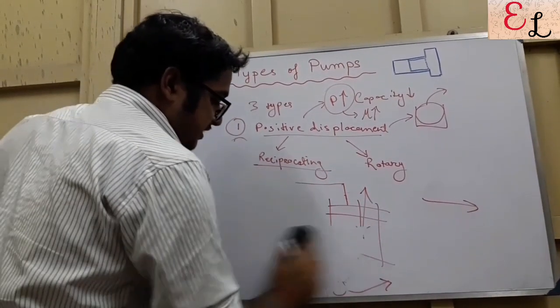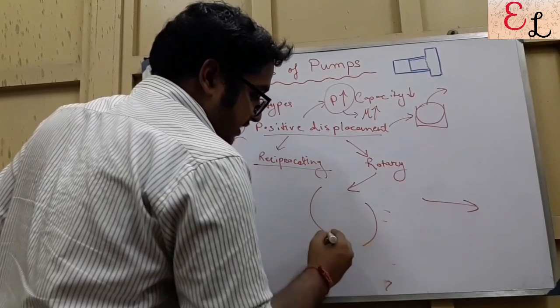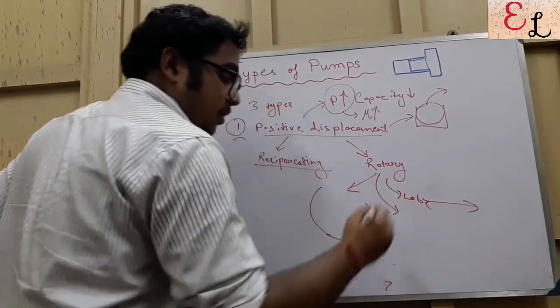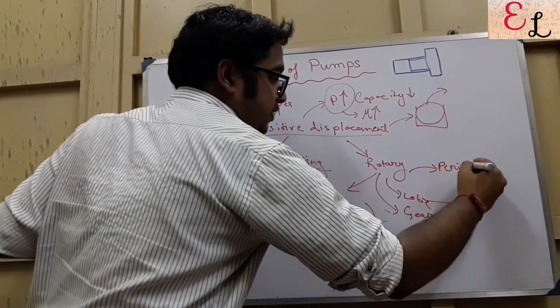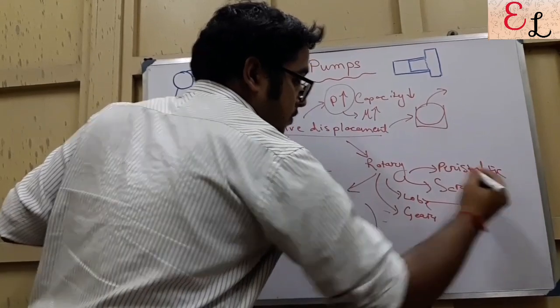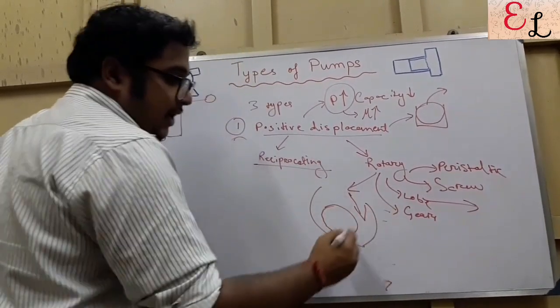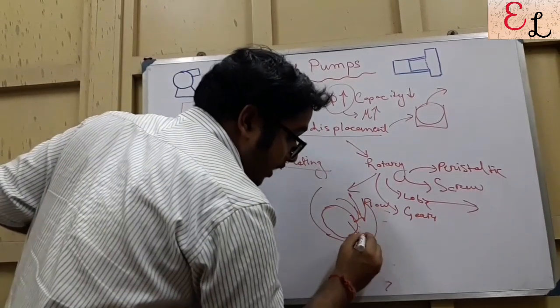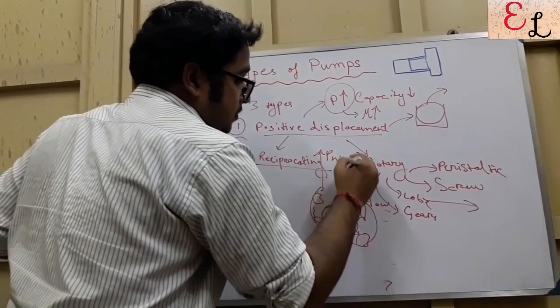For rotary pumps, the subtypes include rotary lobe, gear pump, peristaltic pump — a very commonly used term in industry — and lastly screw pump. All of these function in a similar way. For a rotary lobe, the lobe sucks in fluid at low pressure, then the lobe presses the fluid due to its rotary action, pressing it against the wall to create high pressure. The fluid travels from a low pressure zone to a high pressure zone and gets discharged at high pressure.